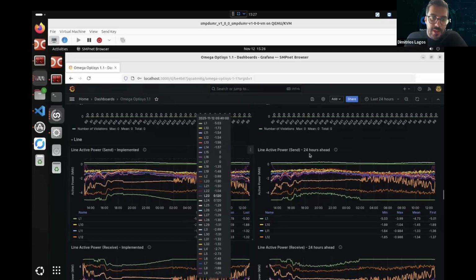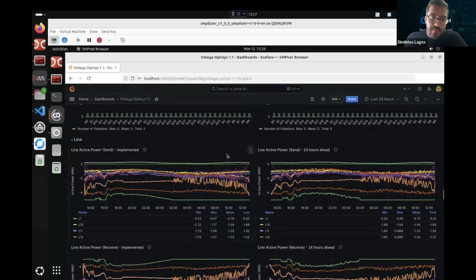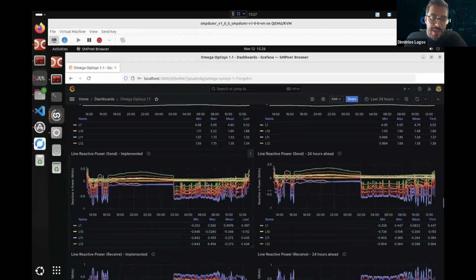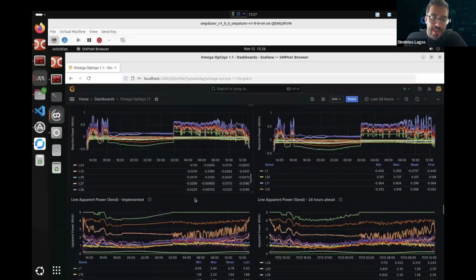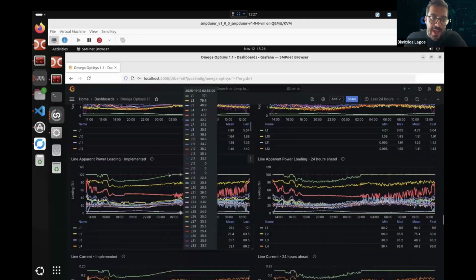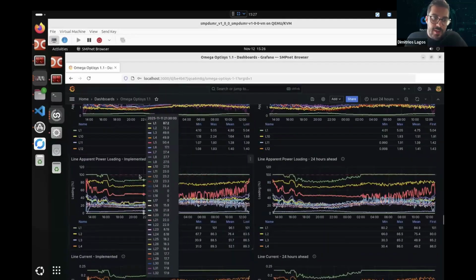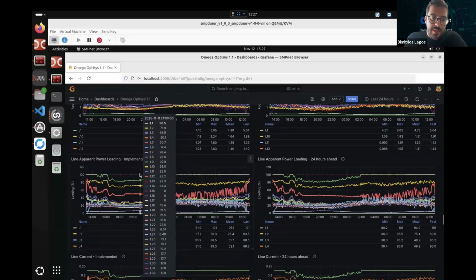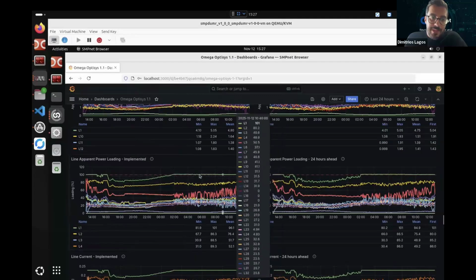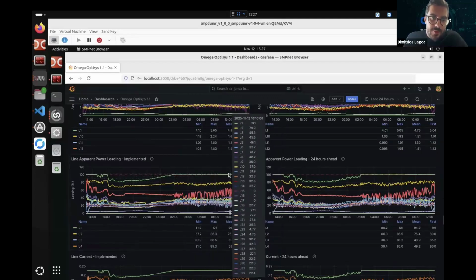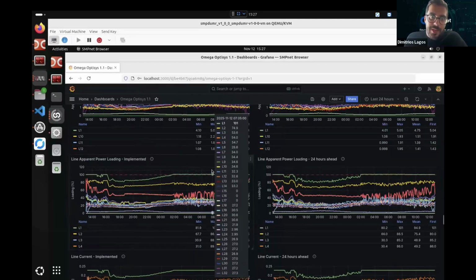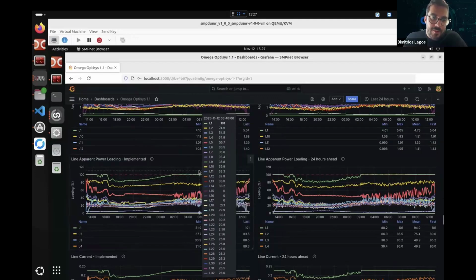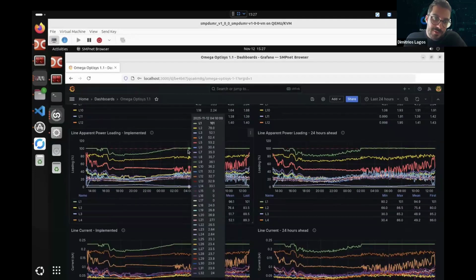In addition, there are different graphs that show the user what is happening on the lines. We have active power, reactive power, apparent power on the lines, as well as the current on the lines. The most important graph, of course, is the loading, which gives the percent line loading. We see that in the same period where we have voltage issues, we also have a congestion incident. That's why we don't see only the utilization of reactive power to resolve the voltage, but also the curtailment of active power, because by using reactive power alone, the voltage issue would have been mitigated, but the overload issue would not have been resolved.